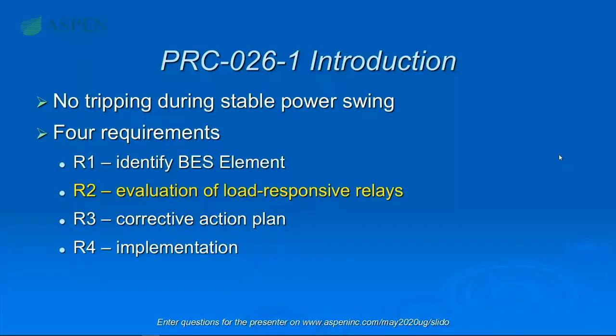The gist of the PRC-26 standard, which is now being enforced, is: if you are the owner or operator of a bulk electric system component — transmission line, generator, or transformer — you are required to prove that your protection will not trip those elements during a stable power swing. There are four requirements; what we'll focus on today is R2: evaluating the load-responsive relays that you have in your one-liner model to see if they will meet the PRC-26 criteria.